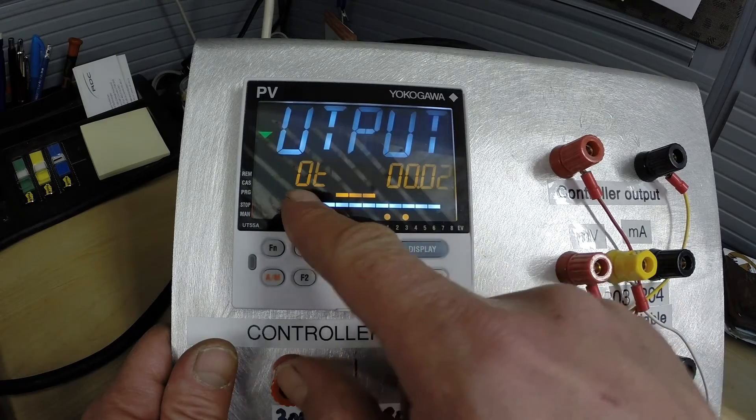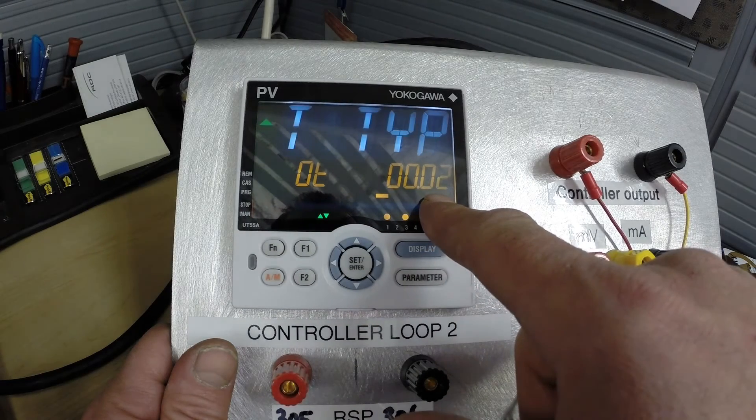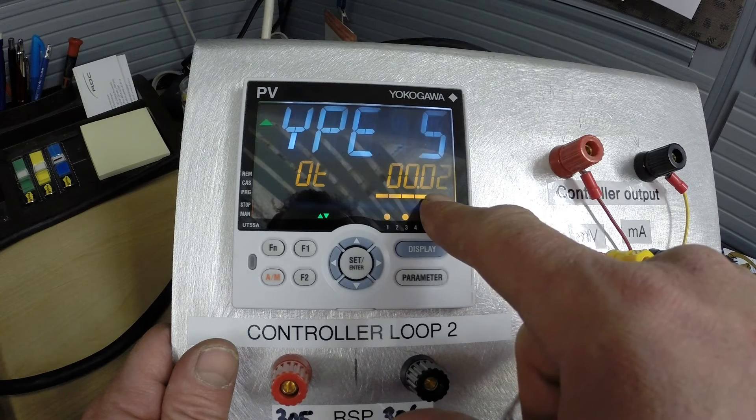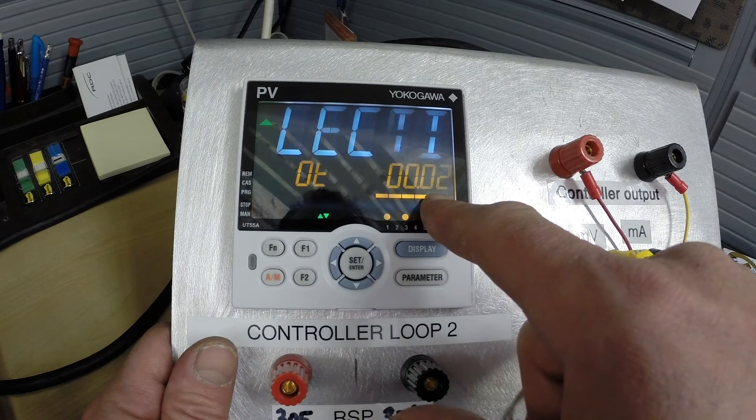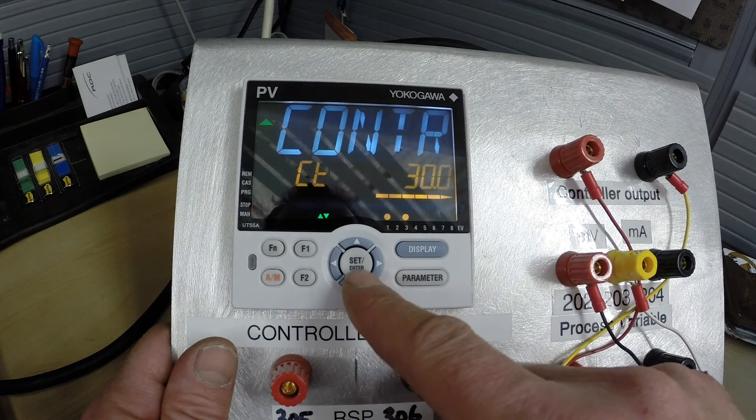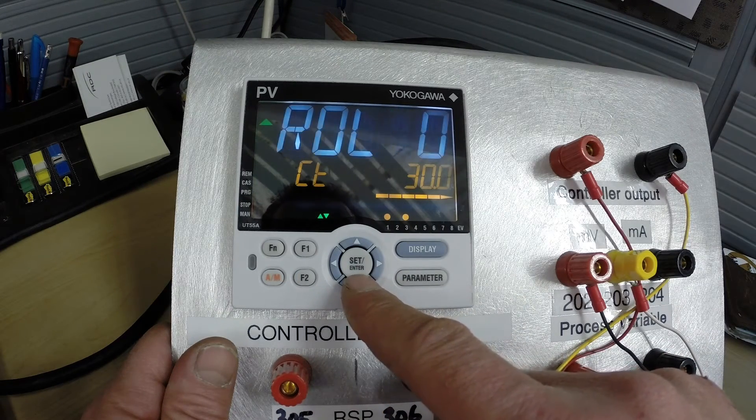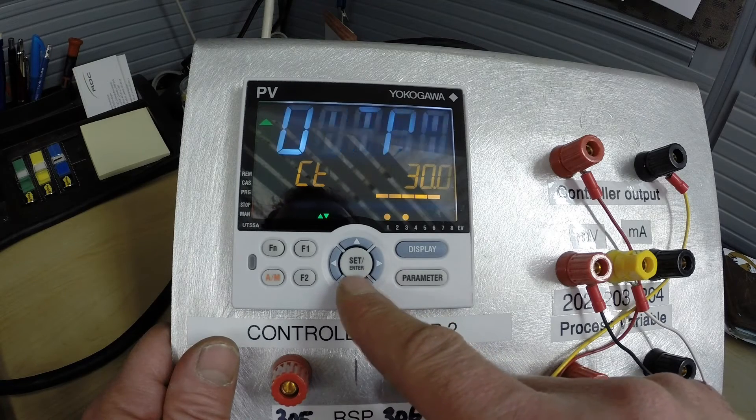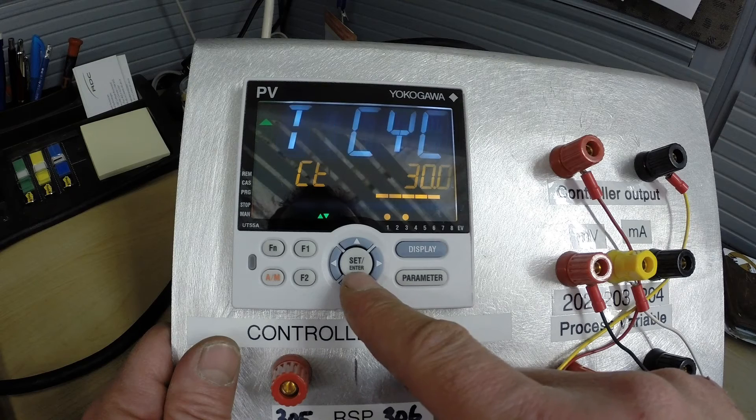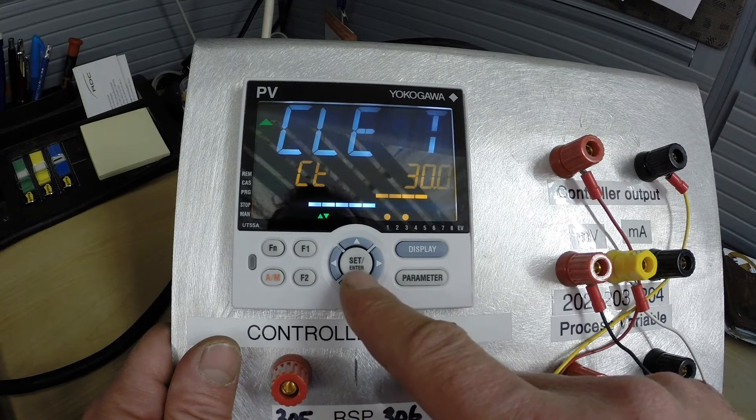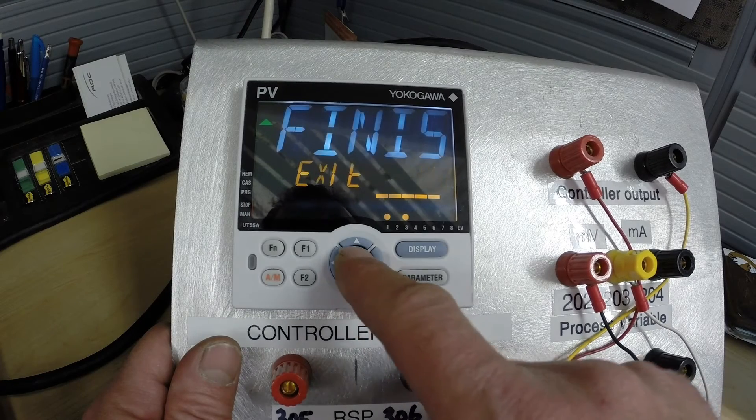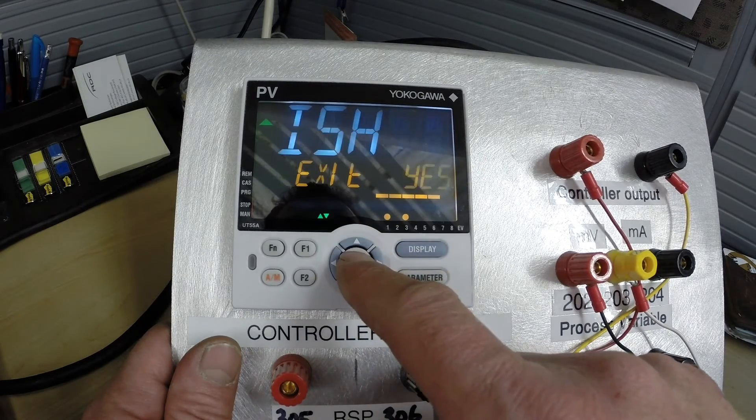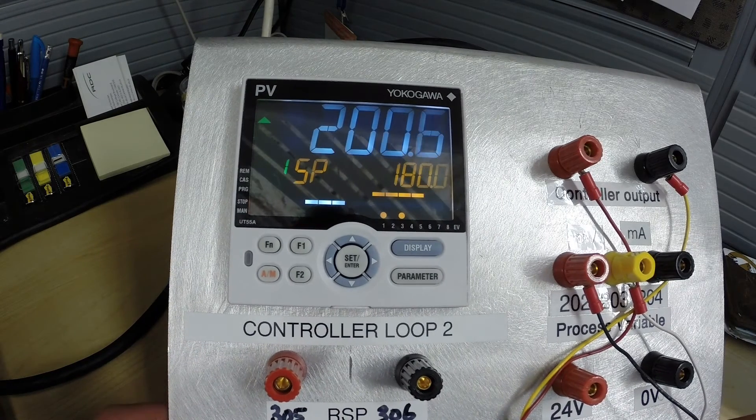Our output in this case here is set at output 2 which is milliamp output which is what we're going to stay with. That will be standard for most situations to drive our final control elements. Cycle time we are not going to change. If we wanted to simulate a slower process or a faster process we could change this value but for what we need to demonstrate we're just going to leave it. Exit. We are done, so let's click yes.